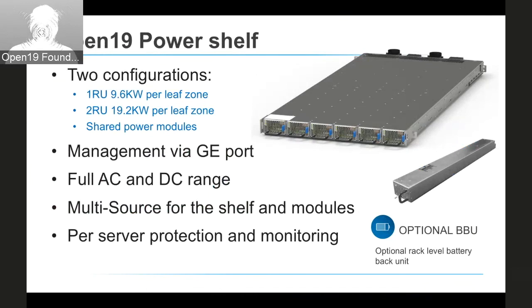Unlike solutions which are now in the industry, which are based on bus bars, when one element is at fault, it will actually take down the whole rack. In this configuration, every element is independent. It goes back to our concept of disaggregation, where we would like to have every element as independent as possible and not affecting the elements around it.